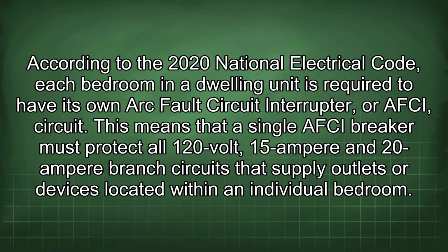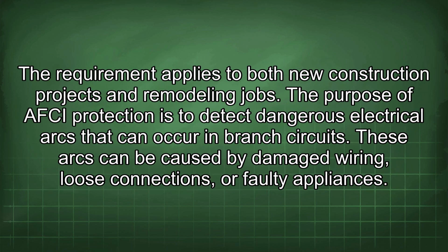According to the 2020 National Electrical Code, each bedroom in a dwelling unit is required to have its own arc fault circuit interrupter, or AFCI, circuit. This means that a single AFCI breaker must protect all 120-volt, 15-ampere, and 20-ampere branch circuits that supply outlets or devices located within an individual bedroom. The requirement applies to both new construction projects and remodeling jobs.